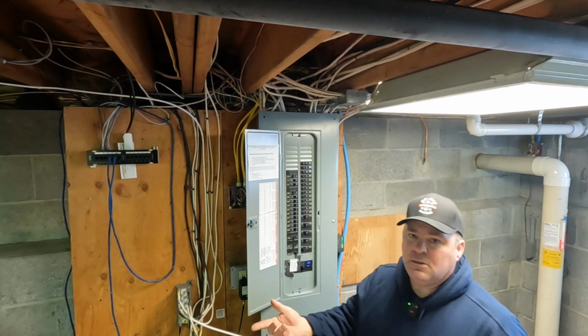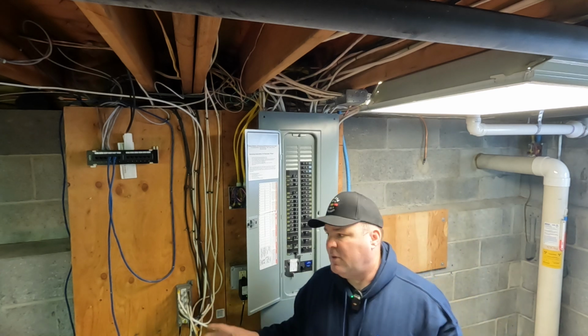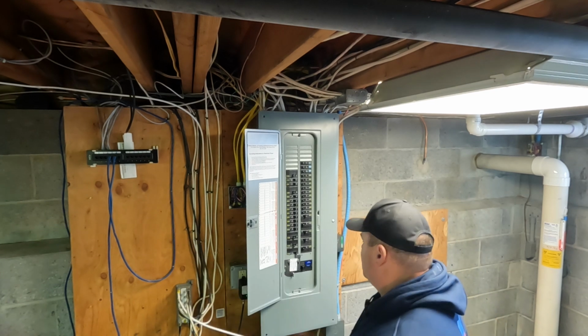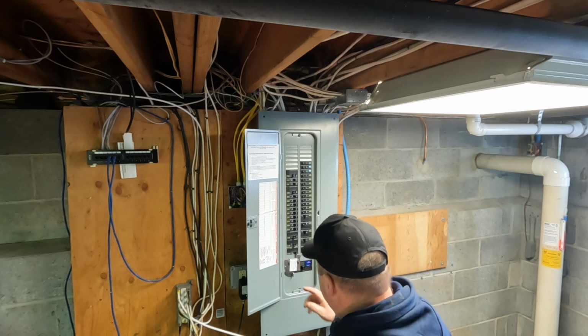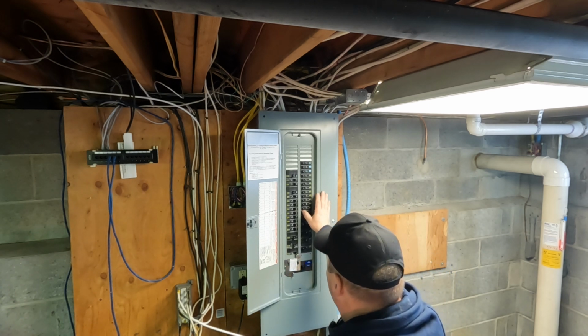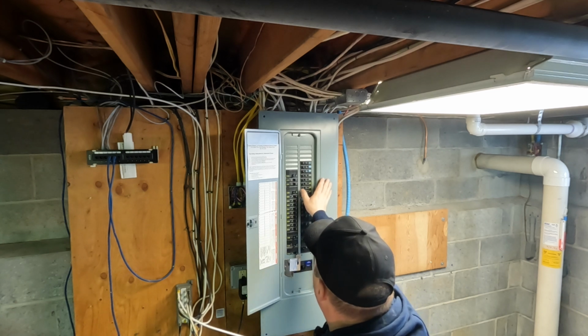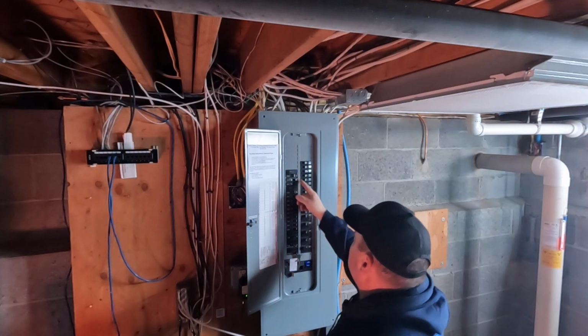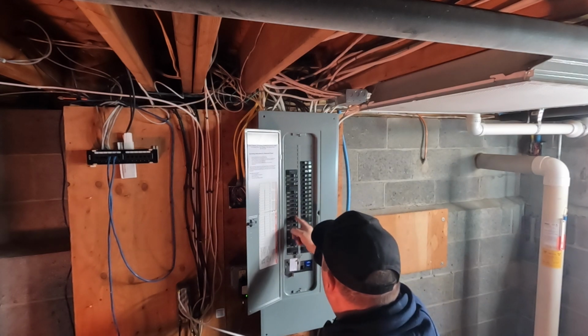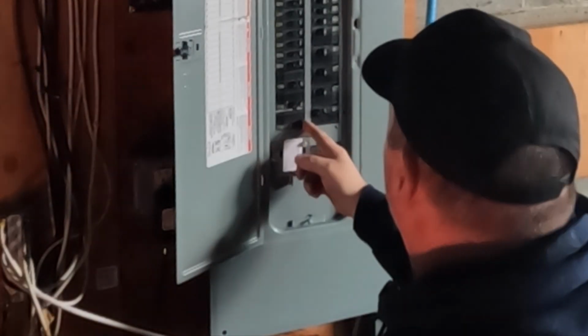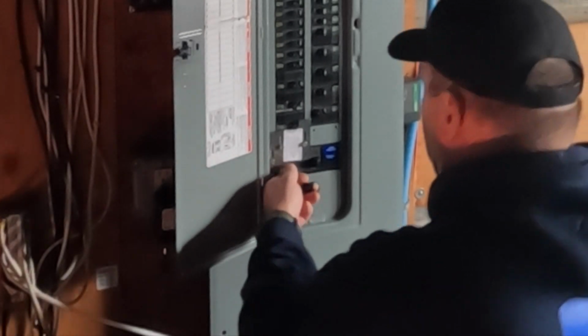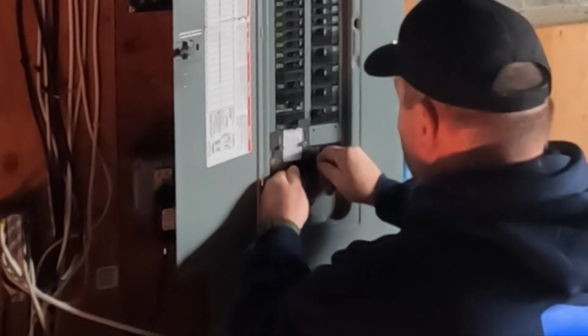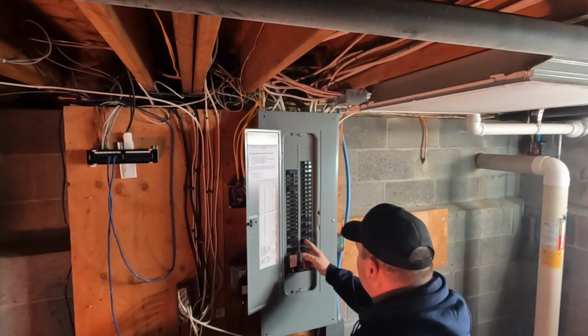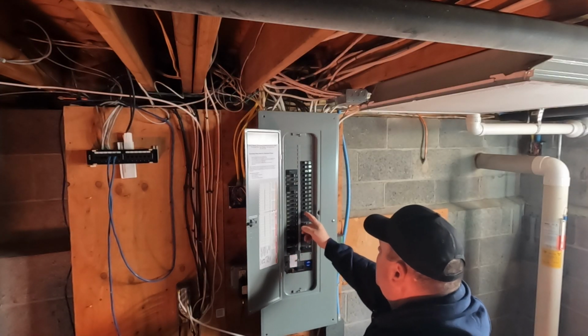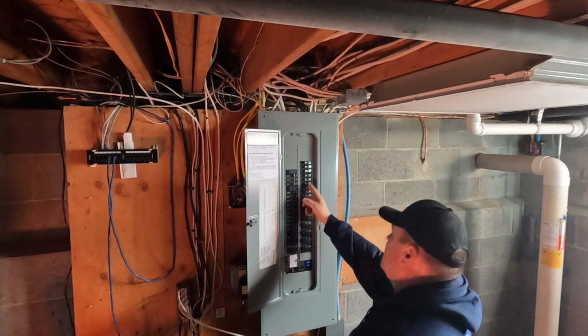All right, so obviously, you heard, we're still on the generator here, and the boiler turned on. We're good to go. So now what I'm going to do is turn everything back off. This is just so we don't damage the generator. And we're going to turn off the generator interlock. We're going to slide the interlock up. We're going to turn the main breaker back on. And we're going to turn all the circuits back on as well. And we will be back on utility power as we were before.